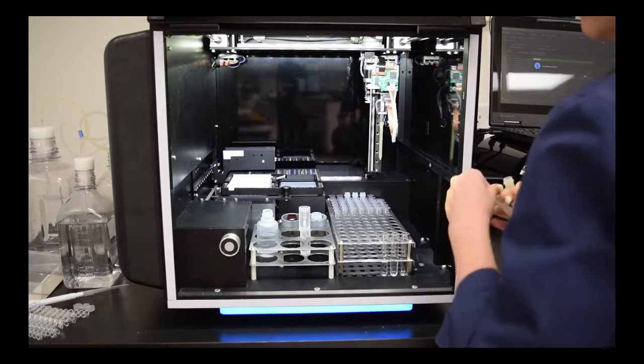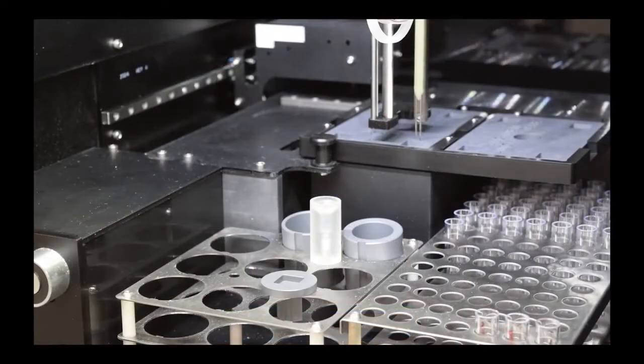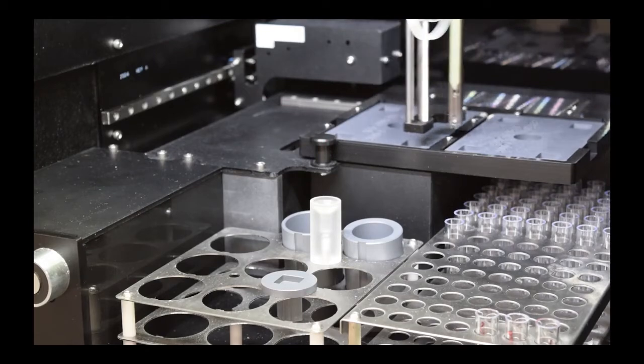Maintenance is minimal and very user friendly. The program will prompt you once a week to conduct an instrument alignment and a reader alignment, along with a probe and instrument cleaning.